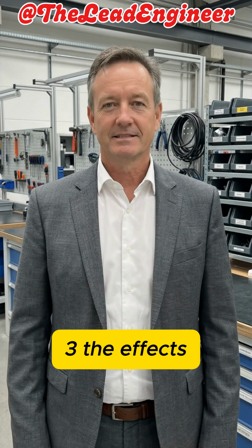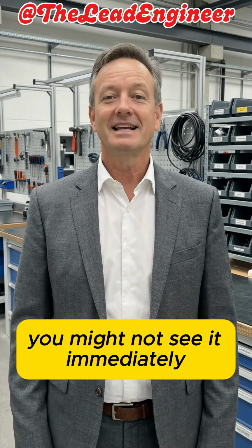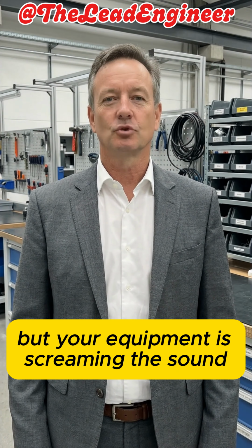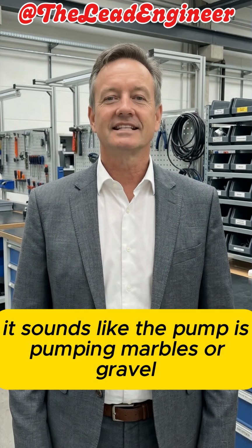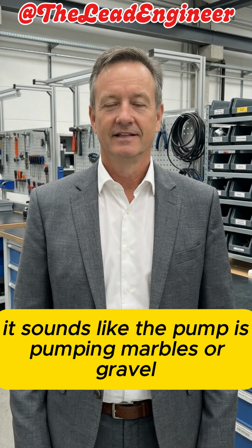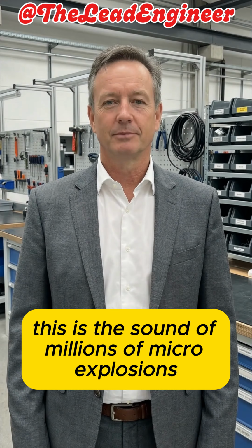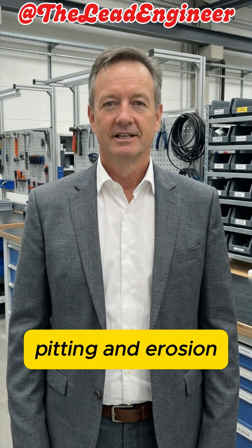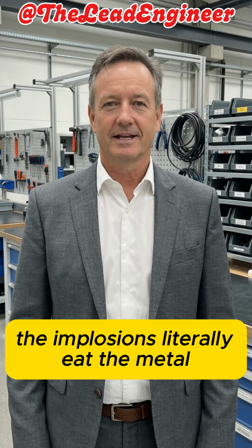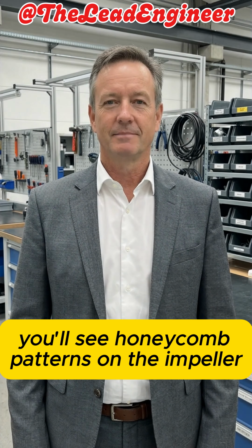3. The effects. Why it's a silent killer. You might not see it immediately, but your equipment is screaming. The sound. It sounds like the pump is pumping marbles or gravel. This is the sound of millions of micro-explosions. Pitting and erosion. The implosions literally eat the metal. You'll see honeycomb patterns on the impeller.